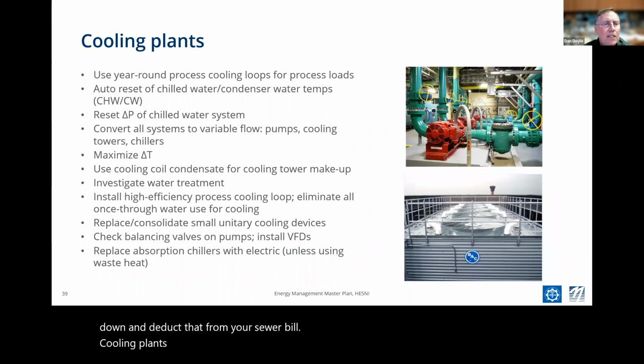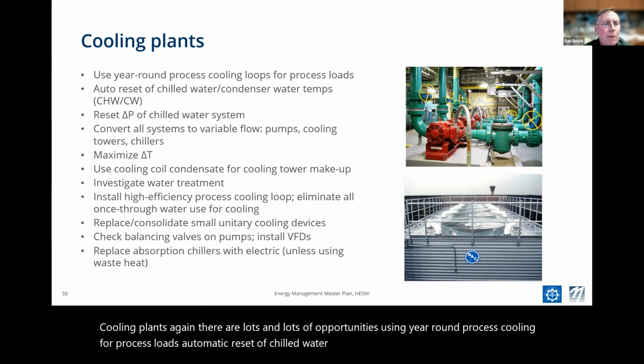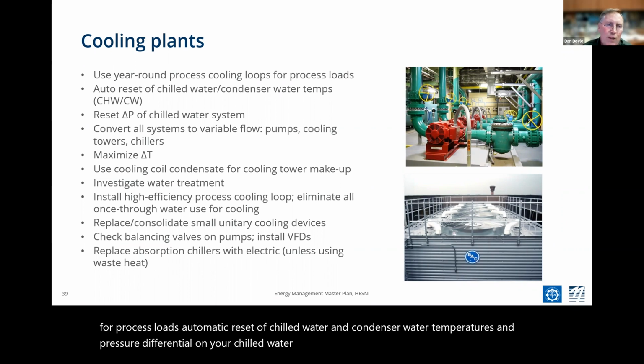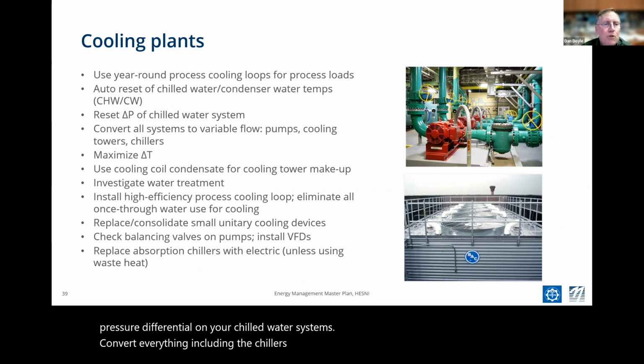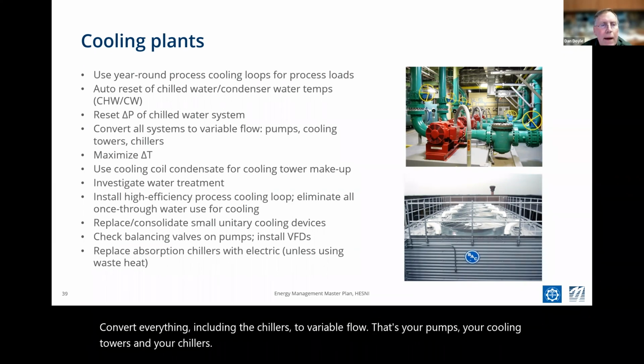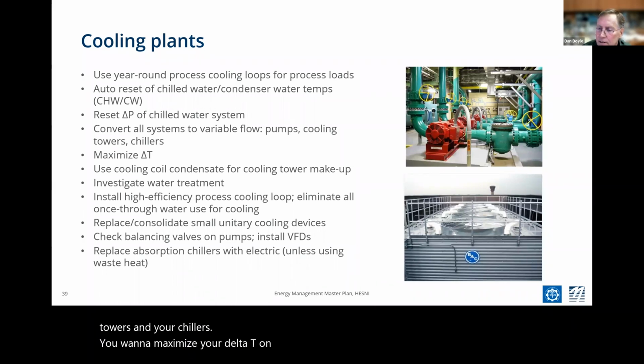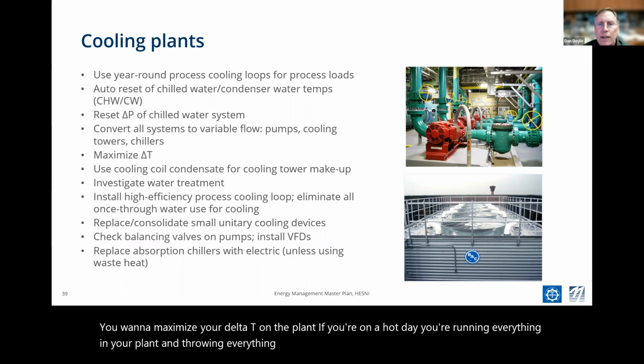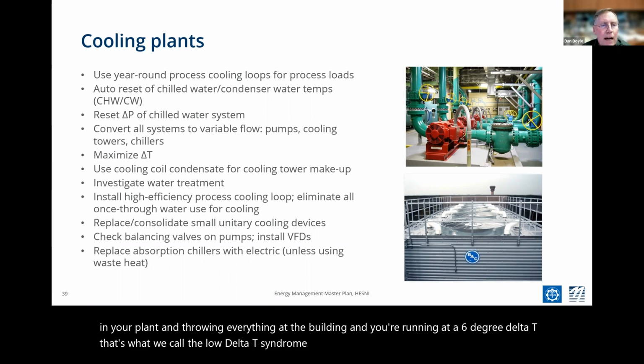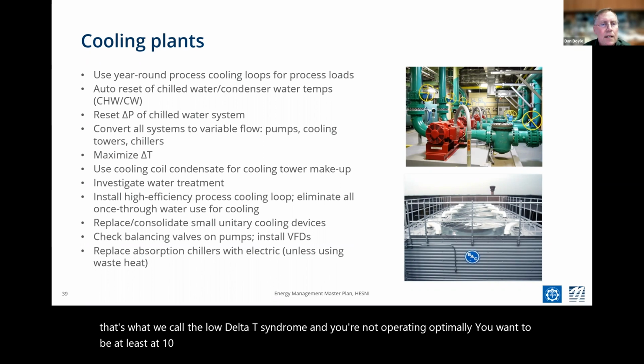Cooling plants, again, there are lots and lots of opportunities: using year-round process cooling for process loads, automatic reset of chilled water and condenser water temperatures, and pressure differential on your chilled water systems. Convert everything, including the chillers, to variable flow. That's your pumps, your cooling towers, and your chillers. You want to maximize your delta T on the plant. If on a hot day you're running everything in your plant and throwing everything at the building, and you're running at a 6-degree delta T, that's what we call the low delta T syndrome. And you're not operating optimally. You want to be at least at 10 or 12 degrees delta T in your plant, or you're not operating efficiently.